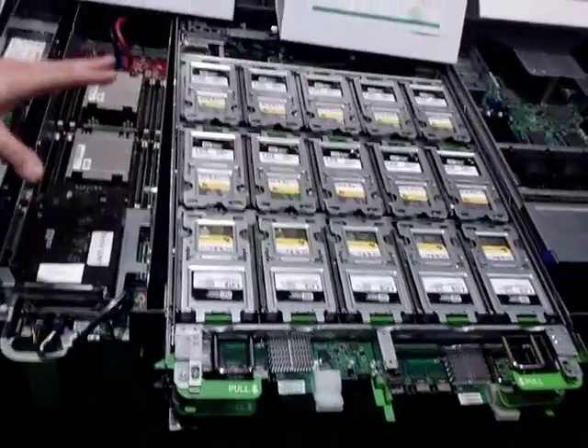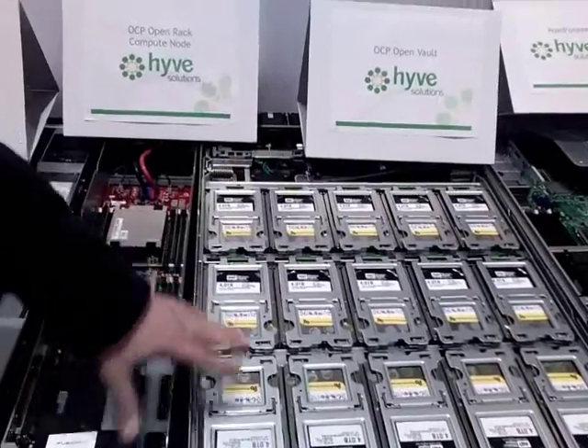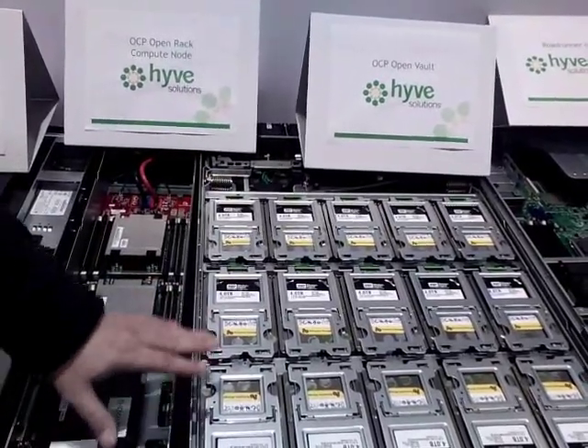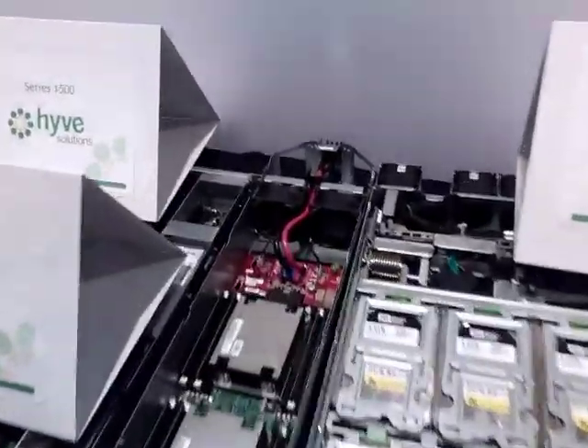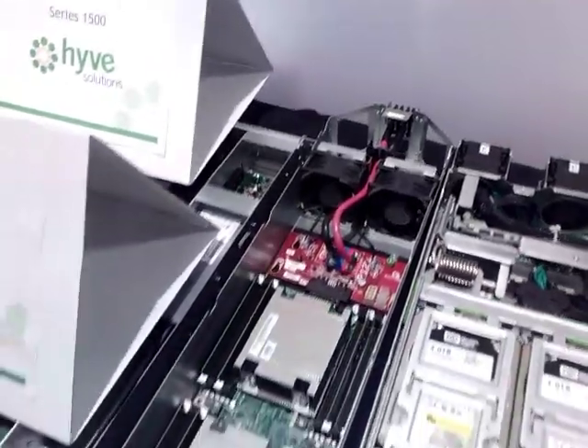Right next to it is its brother, the Storage Open Vault — the storage solution. This is 15 drives per tray, two trays per chassis. The open rack itself currently supports the ability to hold 15 boxes, so you can have 15 storage boxes and/or some combination — up to 45 Winterfells and up to 15 Knoxes in one rack. Each of these slides into the rack and plugs into the bus bar in the back where the power is. The rack consists of three 12-volt DC bus bars — you plug the unit in and it gets power at the back with nothing else required.